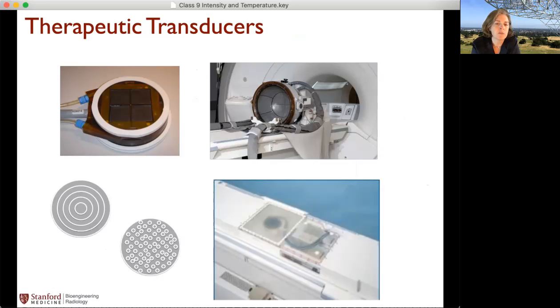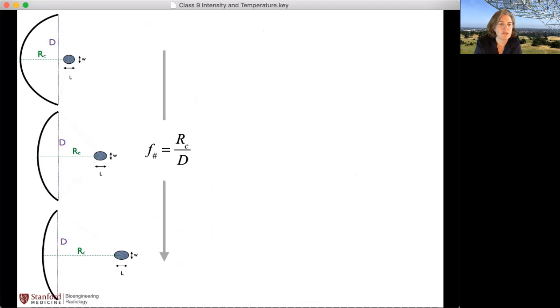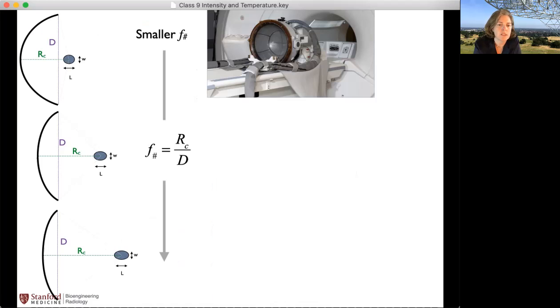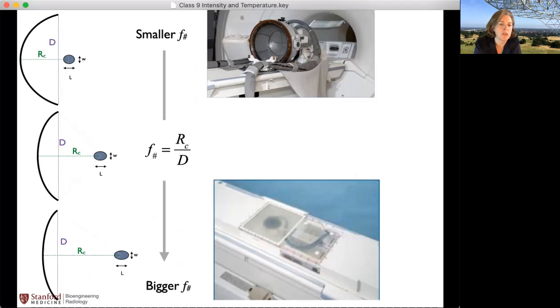And we've talked about there's a number of different possibilities for highly focused transducers. So the Insightec brain system has an F number of about 1. There's the fibroid system built into the tabletop, which has a much higher F number. There's the bone system, which is flat. It's a phased array, so you can curve the phases coming off of that so that you have a focused point. And then you can use a number of other possibilities. So you could use a curved system that has an angular array, or a round system that has randomly spaced elements, for example. And of course, they're going to have different focusing. They're going to have smaller F numbers, as you saw with that system, or maybe larger F numbers, and then they'll have different beam characteristics.